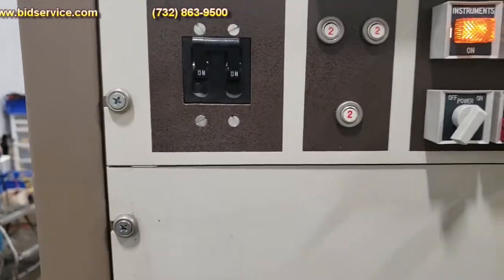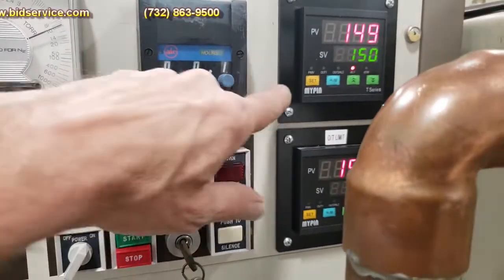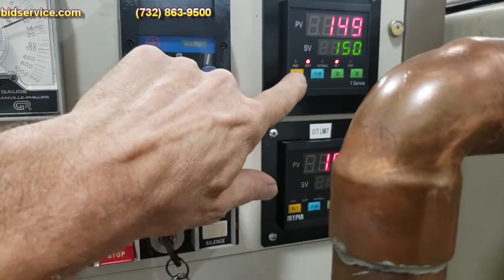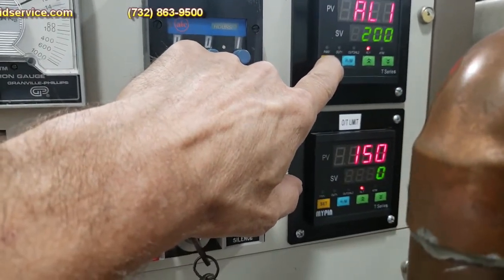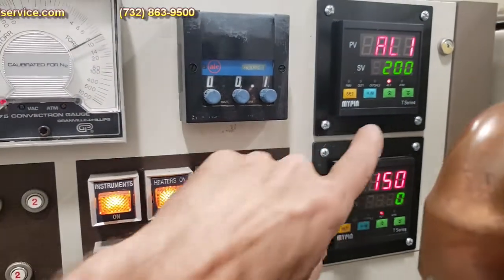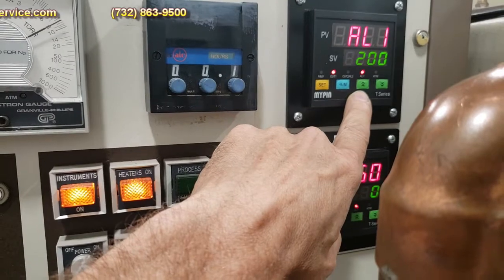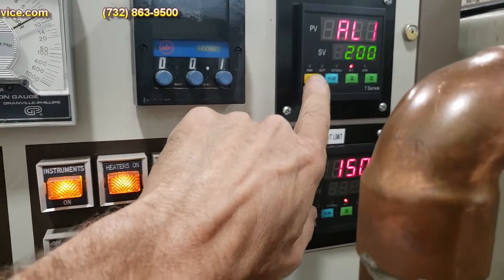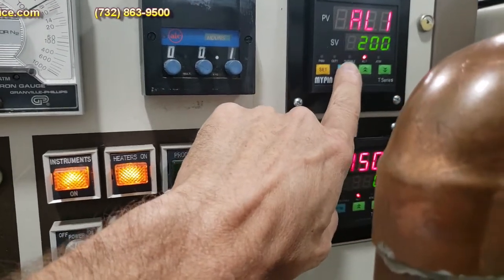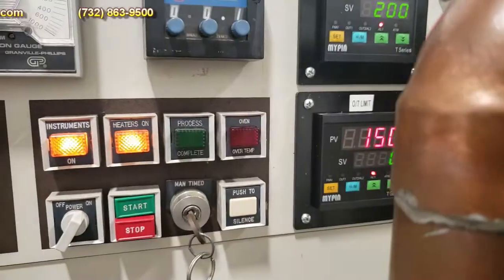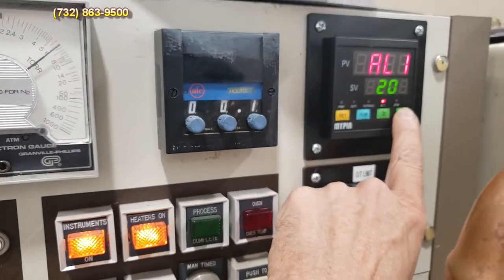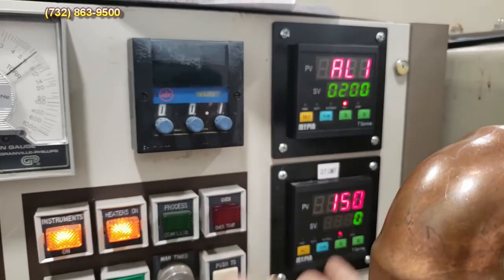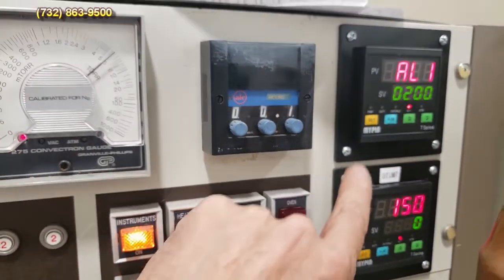Some other things I want to point out about the temperature controller is, again, the upper one is controlling the temperature, and by pressing the set button here for 5 seconds, you can see you do have an alarm 1. So I have it set at 200. And in order to change that, you go ahead and hit the blue button. I'll send you directions on how to operate the temperature controller. I got it off the internet. So this will explain exactly how to use this. Once you touch the blue button, you can go ahead and decrease or increase your alarm, your high temperature limit. We're just going to keep it at 200 for now.